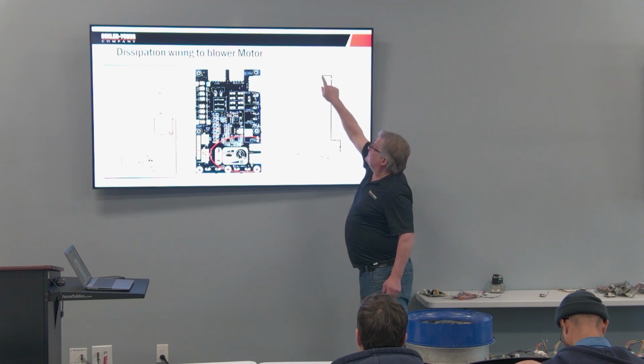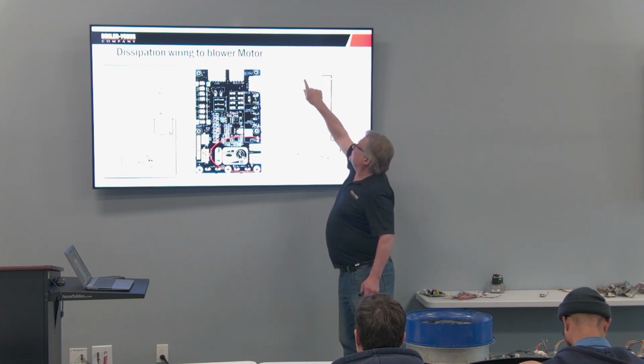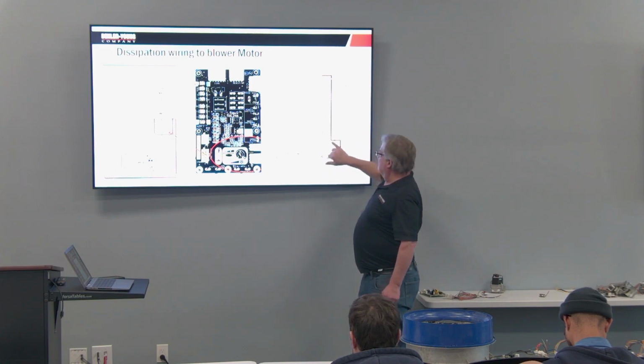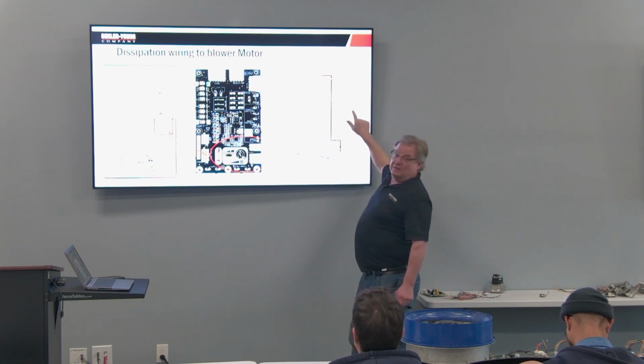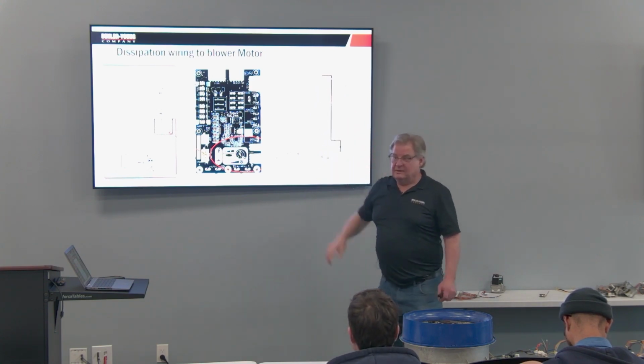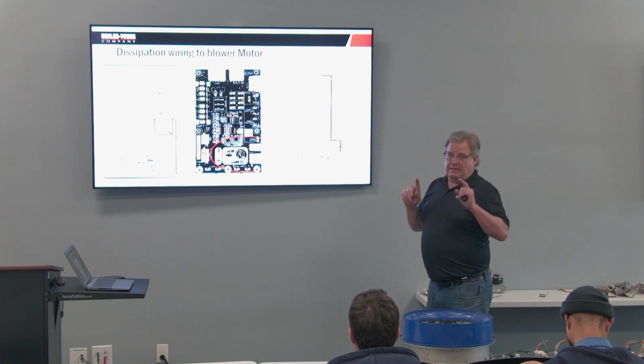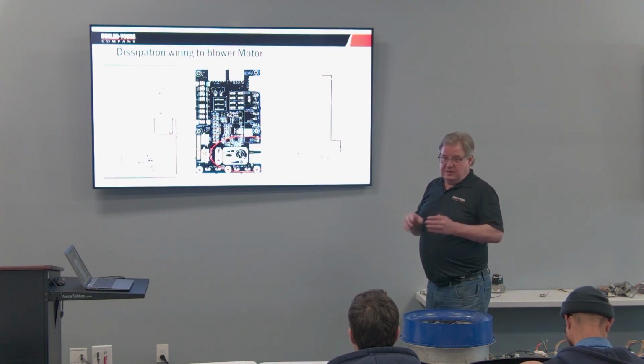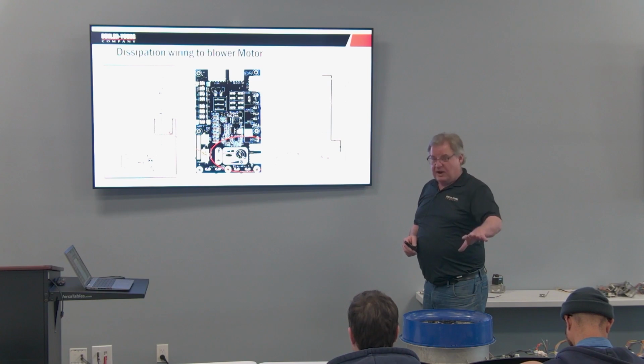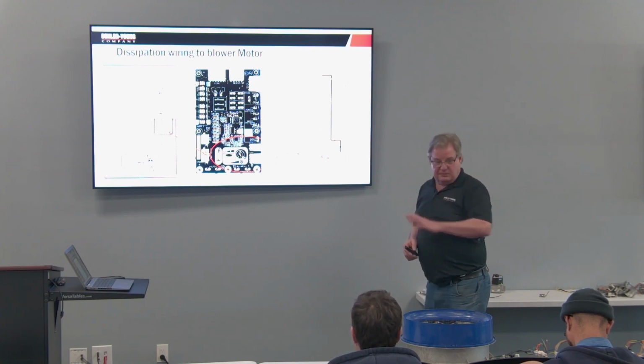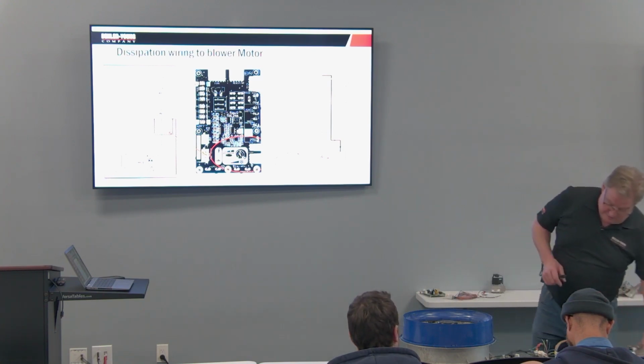Normal operation, it'll come through here. This relay will be closed. So my 9 volts DC would come up this black wire, down the gray wire to the motor. All right. You said this is residential? No. This is commercial. Like I said, the residential is the same board. We have to wire that one in. This is all wired in. This is the same rooftop unit. So yeah, I'm glad you brought that up so I could clarify.